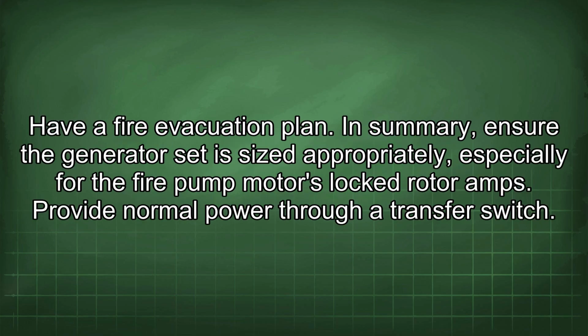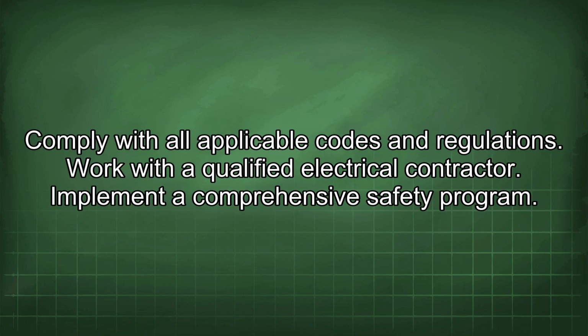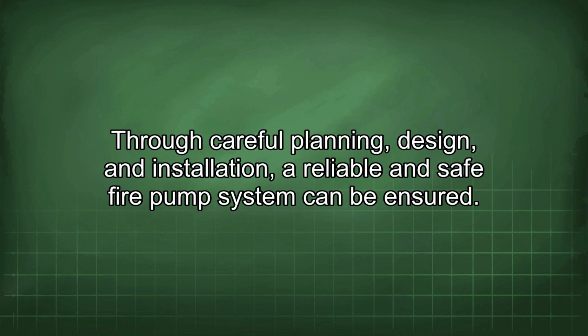In summary, ensure the generator set is sized appropriately, especially for the fire pump motor's locked rotor amps. Provide normal power through a transfer switch. Comply with all applicable codes and regulations. Work with a qualified electrical contractor. Implement a comprehensive safety program. Through careful planning, design, and installation, a reliable and safe fire pump system can be ensured.